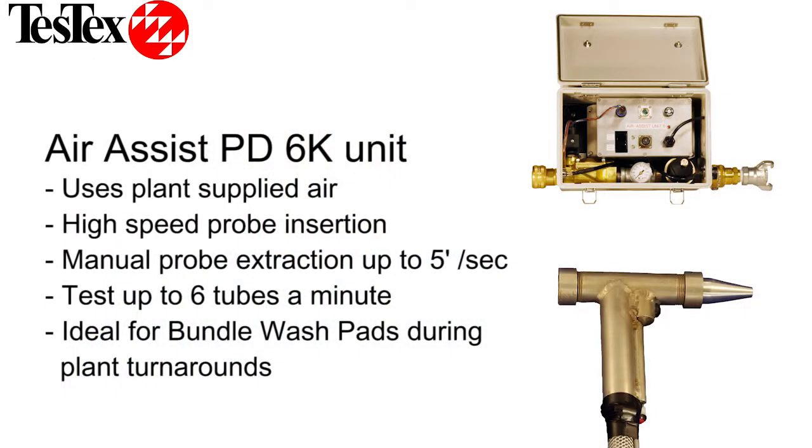TesTex's high-speed inspection includes the PD-6K. Using plant-supplied air, we can test up to six tubes a minute, or 1500 to 2500 tubes per team per shift. Our insertion gun shoots the probe down the length of the tube quickly, and a technician pulls it back through at up to five feet per second. This technology should be on every bundle wash pad during a plant turnaround.